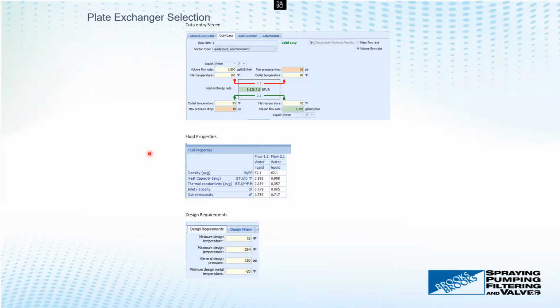In plate heat exchangers, when we select a plate, it has to be corrosion resistant. There's no allowance like in shell and tube, where you can keep adding corrosion allowance on the tubes. That's not the case in plate heat exchangers. If they are thin plates, it has to be a corrosion resistant material. Anything which is pressable can be used as a plate material.